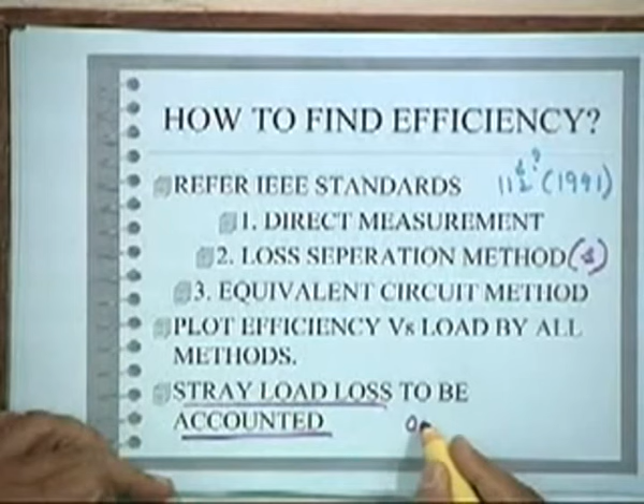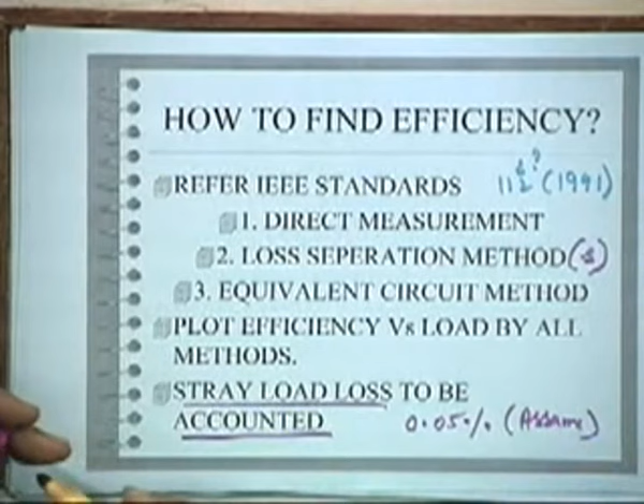Of course, the one thing that they take is they take it to be 0.05% of the output, right. So this is one of the assumptions, because there has been a lot of discussion in international conferences on how to get stray load losses, because in under loading conditions the magnetic fields will change, and the stray load loss is a matter of practical concern. Okay.